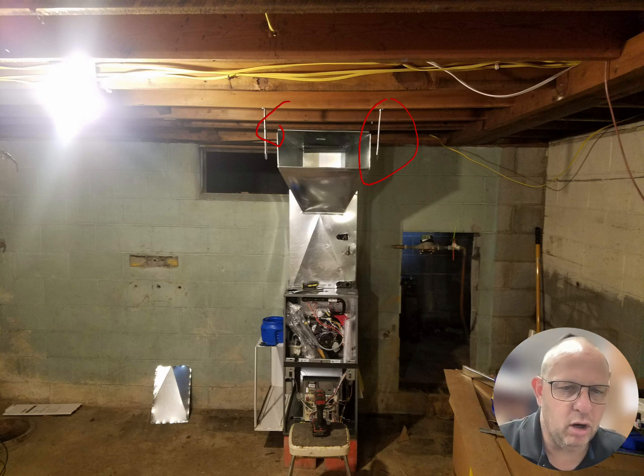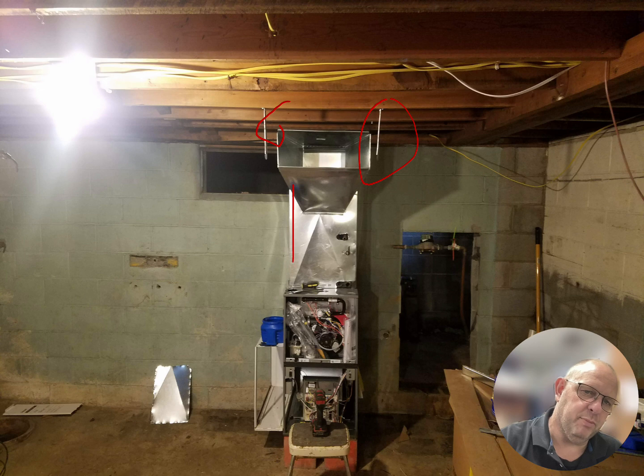And then we'll go along the actual seams of that ductwork and we'll put a special type of caulk on a brush, which is referred to as the mastic caulk. Very flexible, lasts for a very, very long time, longer than any tape would or any duct tape would on that particular unit. We see our plenum coming off of our furnace.